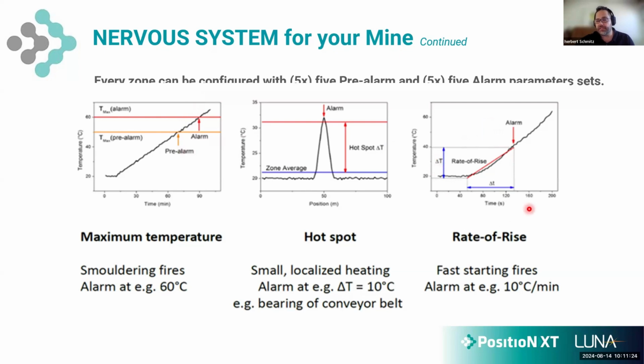And then from a fire detection perspective, we can use rate of rise alarms. If we see that the temperature at this crosscut is suddenly going up faster, or there's a rapid change in temperature within that environment, we can create a pre-alarm condition to go and investigate. And if that keeps on continuing, that can go into an alarm, indicating exactly where that point of thermal energy is. Now, all these alarm parameter sets work together to create a unique alarm grouping. We can set up different alarms for the cold air section, the exhaust section, depending on the air movement through a haulage, within an electrical substation, within a refuge chamber. We can set up unique monitoring parameters for each of those sections throughout the mine.